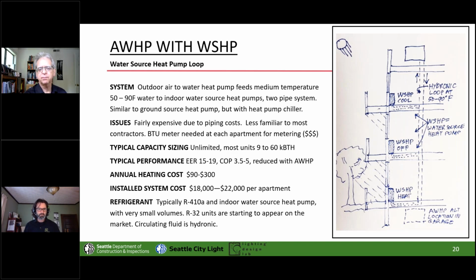So in case that went by some of you, the unit on the top that I forgot to label there is an air to water heat pump, and it's heating or cooling the water in that loop depending on the need to keep it in that 50 to 90 range. And all the refrigerant we're talking about is contained in the unit or in the other little units. And then the actual piping lengths, instead of being refrigerant with that leakage problem, this is hydronic, and as long as that stays in that 50 to 90 range, then there's heat for the individual units in the apartments to be pulling heat out or putting heat back into that loop. Did I say that right? Heating and cooling would be putting heat back into that loop. So every apartment gets its own temperature control. There's no switchover issue, like my building was in heating, but the one with sun wanted cooling.